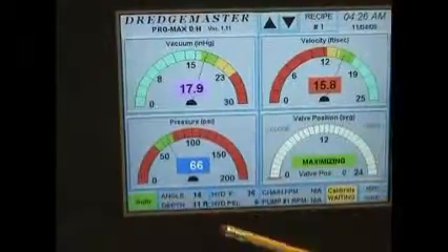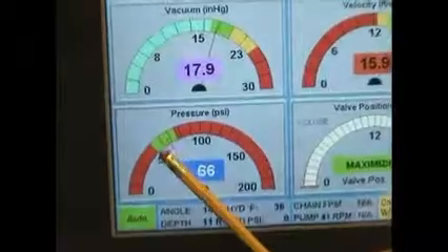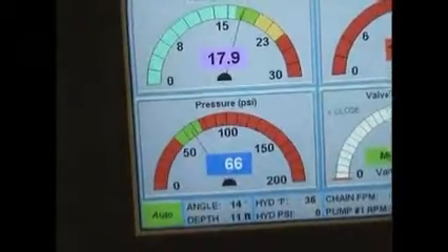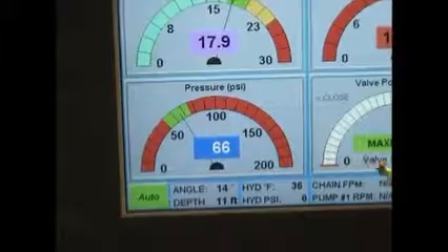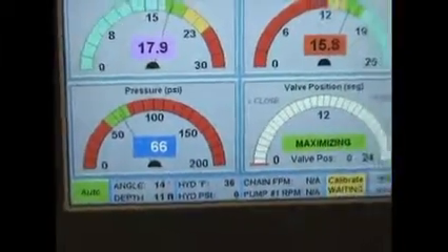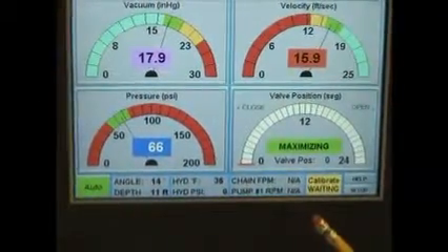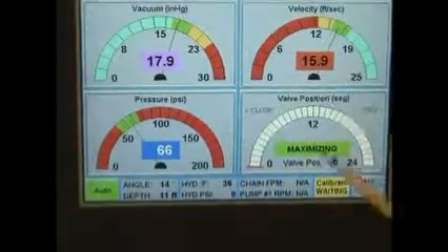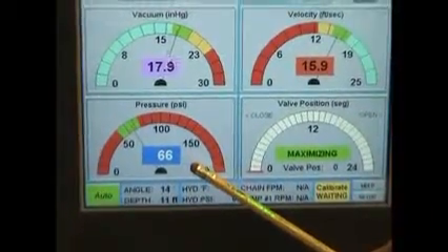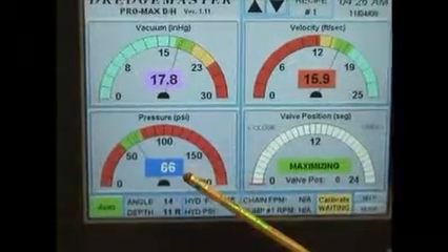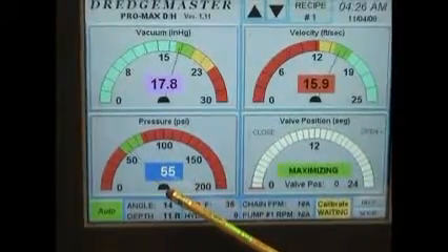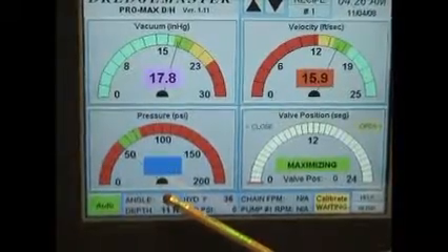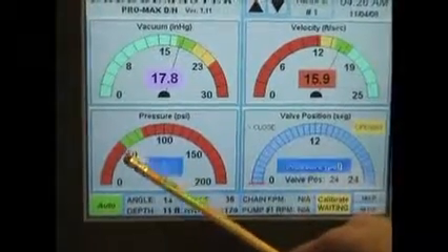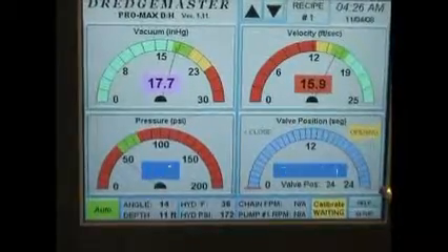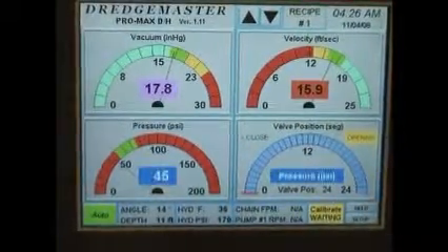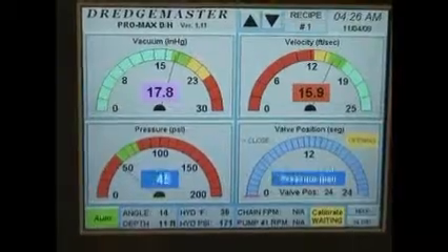Okay, the next gauge we're going to look at is our pressure gauge. Again, our green zone area is an area where we have good production, not endangering the pipe to plug. So as you can see, our valve is closed. Let's start to simulate a condition where the pump is starting to cavitate for whatever reason. Our pressure is going to start to drop, and it probably is going to drop rapidly. And as soon as it gets into our lower red set point, our valve immediately opened up. This prevented a cavitation from happening at the pump.